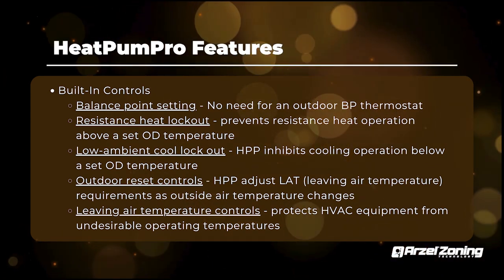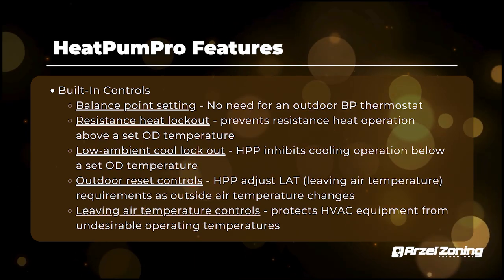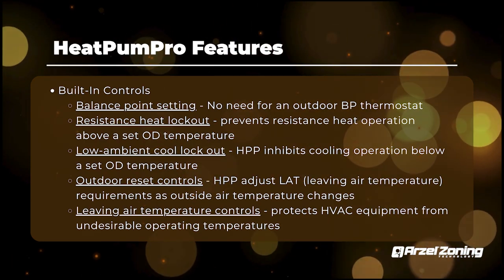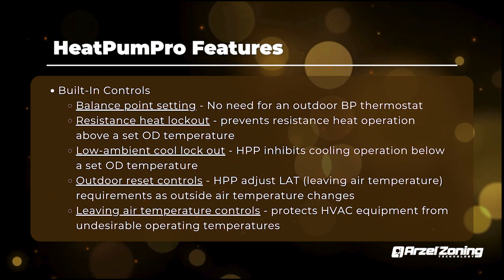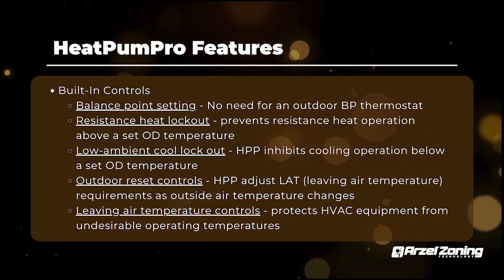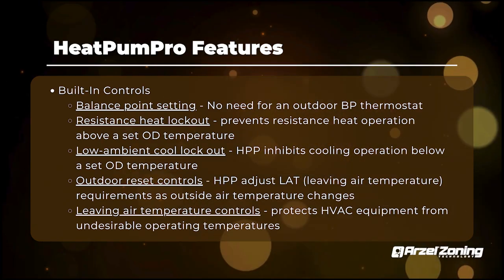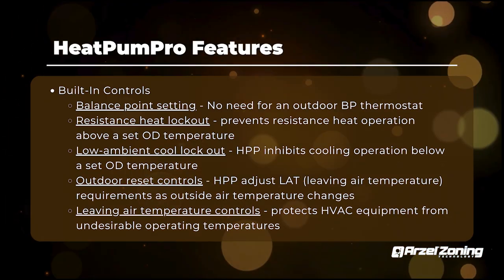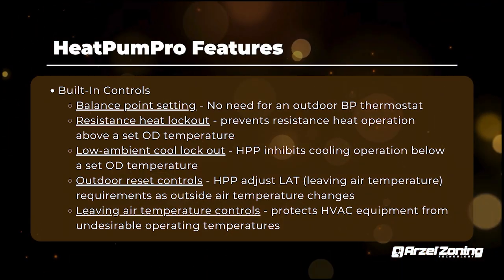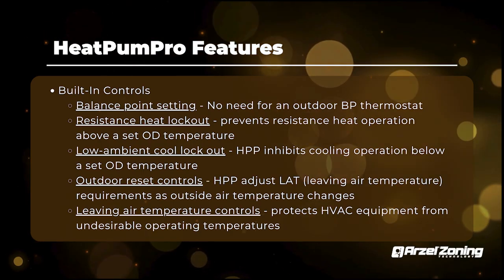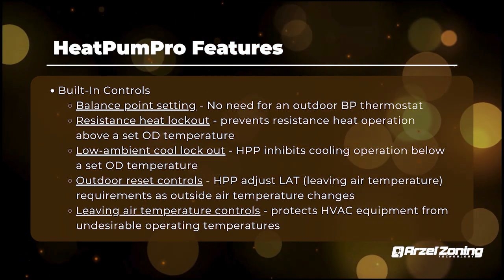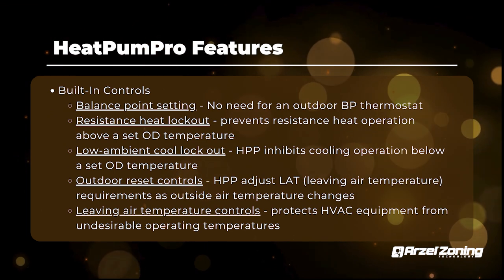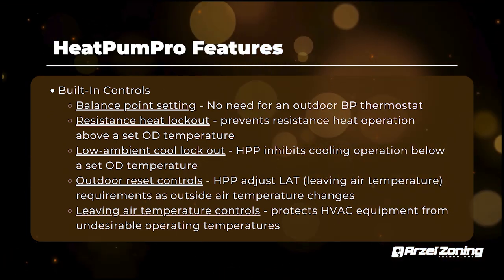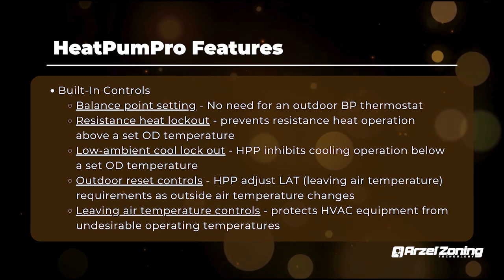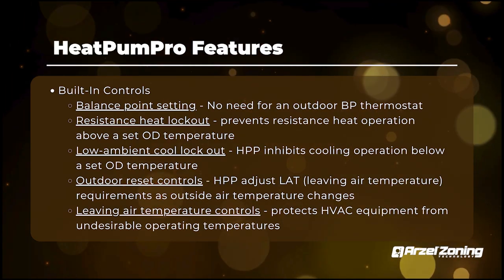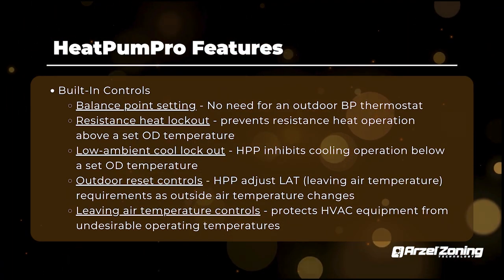It also comes factory with a low ambient cooling lockout. Essentially, what that prohibits the customer from doing is if by chance you're in the middle of winter, a kid flips one of your thermostats to cooling mode and it's too cold to physically engage that compressor, it'll actually prevent the condenser from running. And that's a field settable temperature from 50 degrees down to 0. So you guys can change that. And then that just prevents equipment damage, so flooding of the compressor in the middle of winter. Because if you got a zoned house, you may have 6 or 7 zones in there. You may not realize that that zone's set to cooling for a day or two before you're in that area of your home. So it just gives them a little bit of added comfort and safety, I guess, for their equipment.